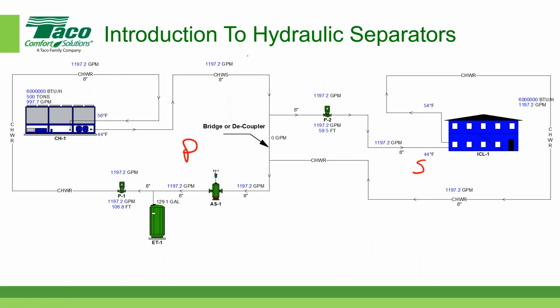Okay, so that was when the primary circuit was equal to the secondary circuit. And let's do a different one here. Let's assume for a moment, again, we're starting with 1,200 rounding the corner here. But this time, we don't need 1,200 in the secondary circuit. Let's say the demand on the secondary side is only 600 gallons per minute. So it goes out here at 600, goes through the load, comes back at 600.